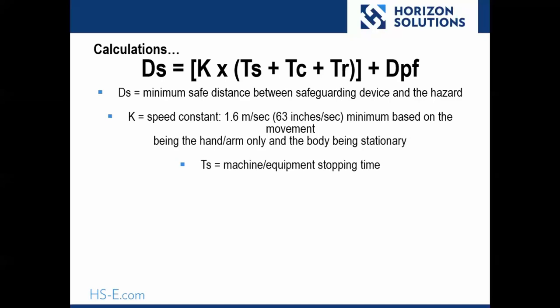TS is the total machine stopping time, where TC represents the control system stopping time or response time, and TR is the response time of the safeguarding device itself as well as any interface it may have.